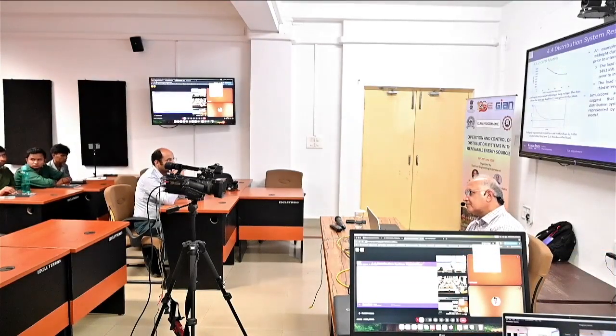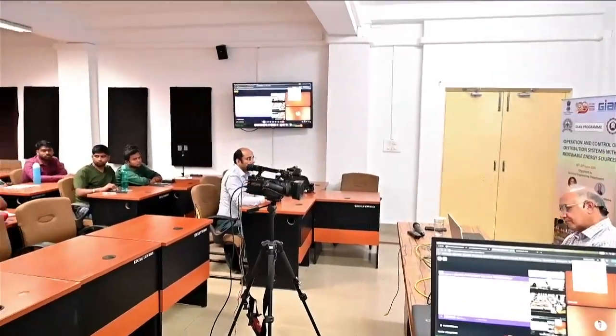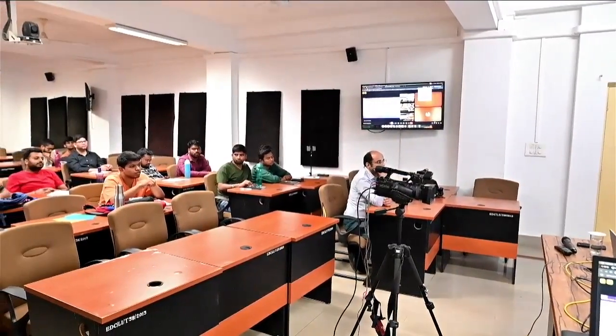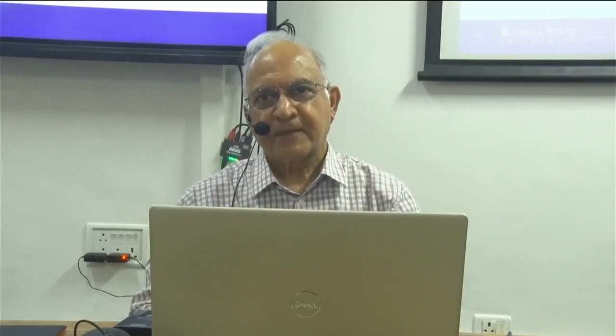And the load varies sometimes, like one example said 45 MVA and then another simulation was 36 MVA. So are these data from simulations? No, this is based on your own judgment, because as I said, the transformer maximum loading is 30.